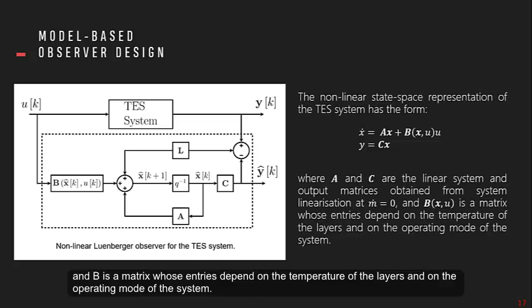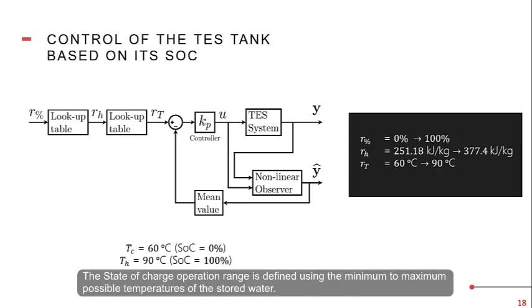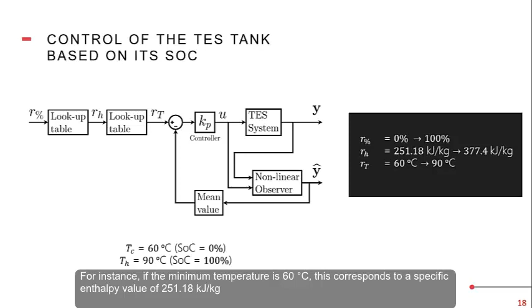The state of charge calculation adopted in this work makes use of the available temperature measurements. The state of charge operation range is defined using the minimum to maximum possible temperatures of the stored water. For instance, if the minimum temperature is 60 degrees Celsius, this corresponds to a specific enthalpy value of 251.18 kilojoules per kilogram, and the thermal energy storage is fully discharged. Conversely, the thermal energy storage is fully charged at a maximum temperature of 90 degrees Celsius and a specific enthalpy of 377.4 kilojoules per kilogram.